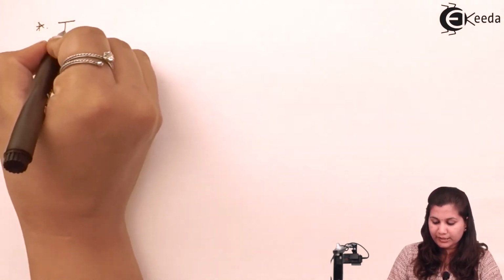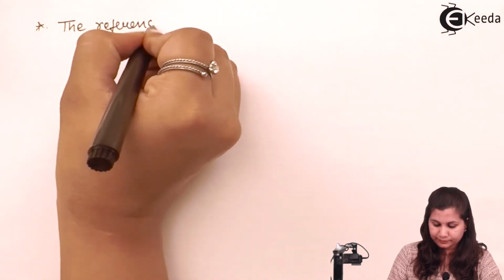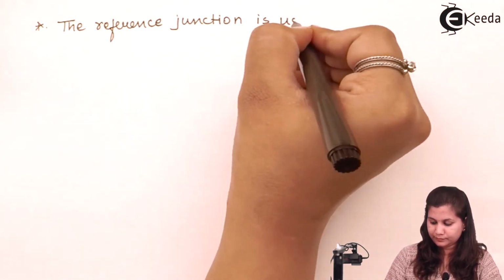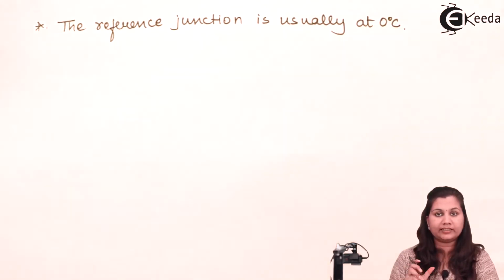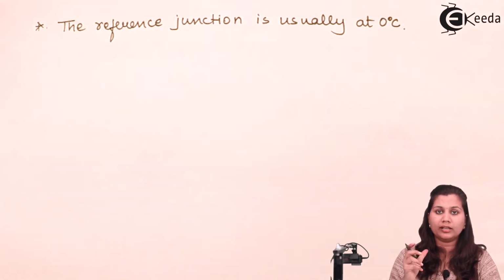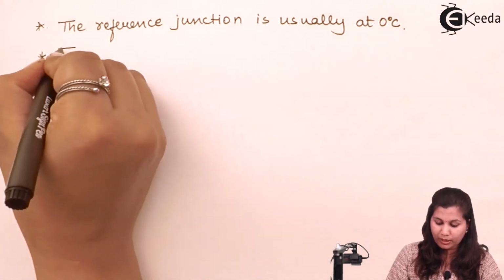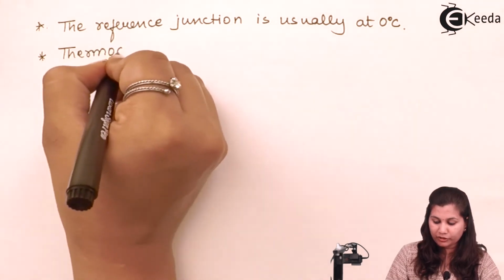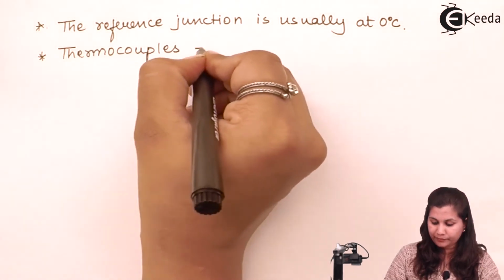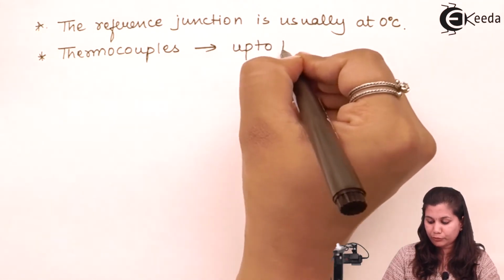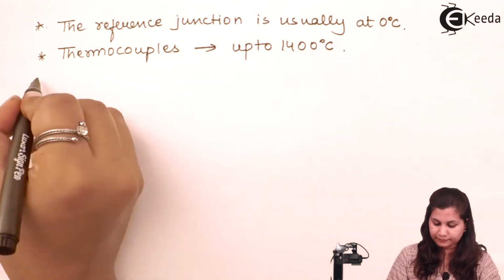Now in this thermocouple, as I've said, we have two junctions, reference and measuring junction. The reference junction is called the cold junction and the measuring junction is called the hot junction. This reference junction is usually 0 degrees Celsius. So directly the temperature difference will be indicated on the indicating device. Now, thermocouples are used for temperature measurements up to 1400 degrees Celsius.